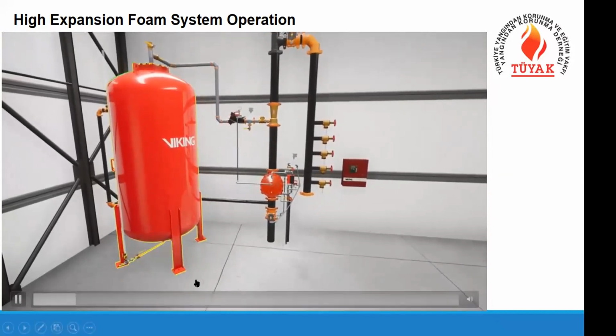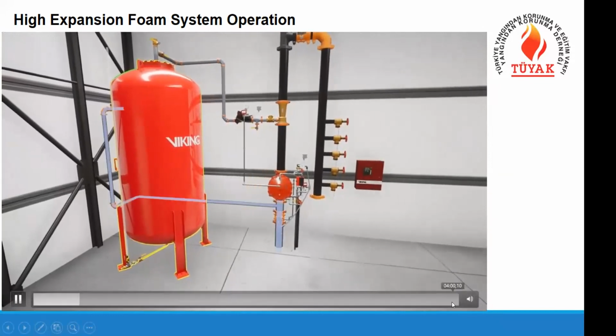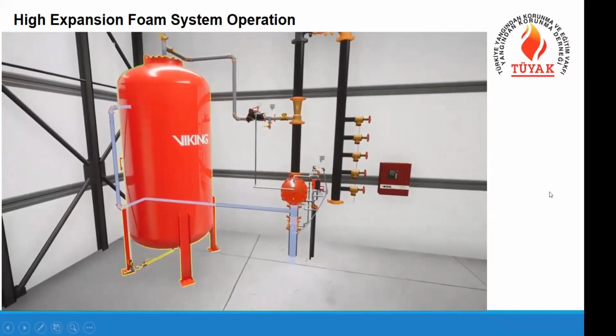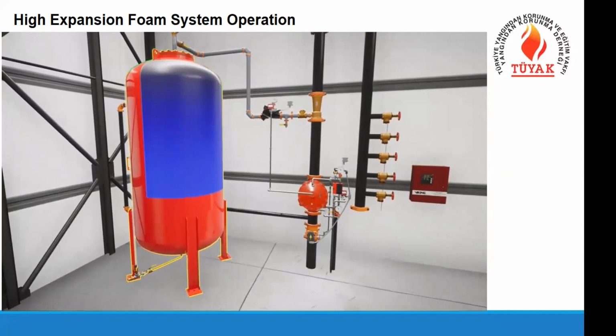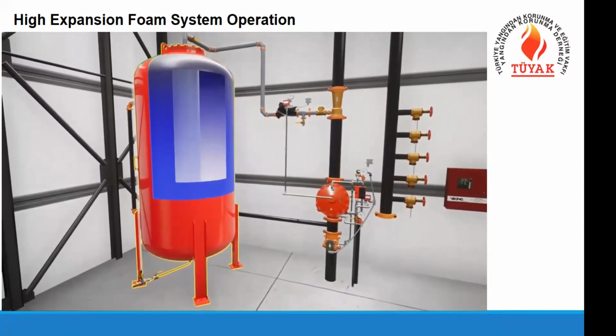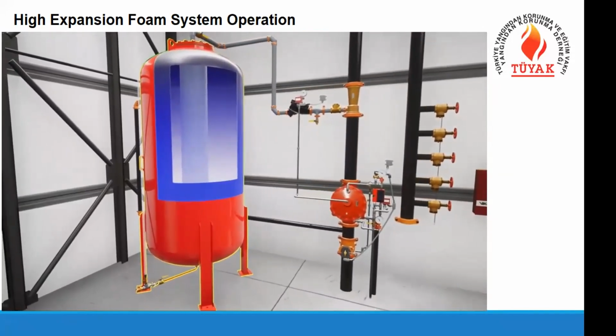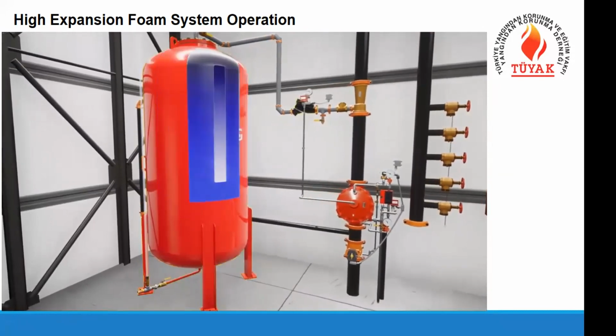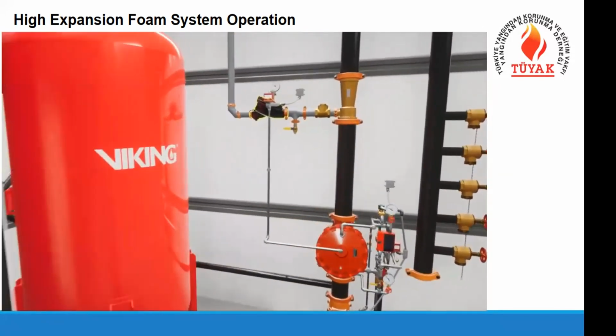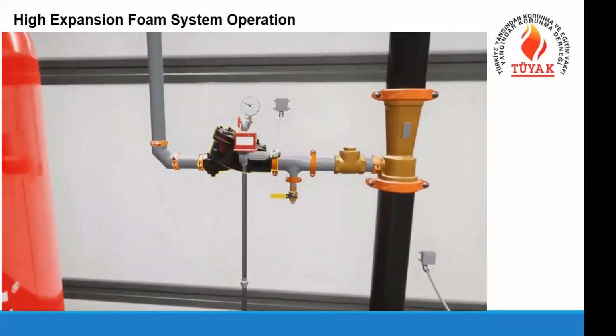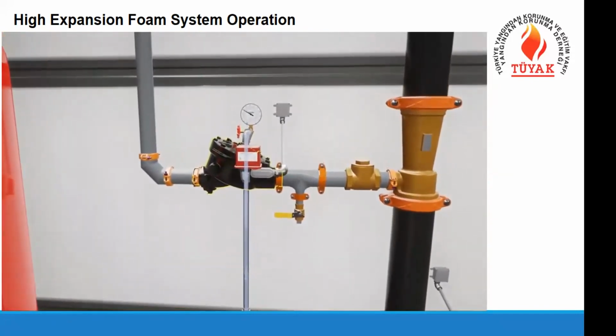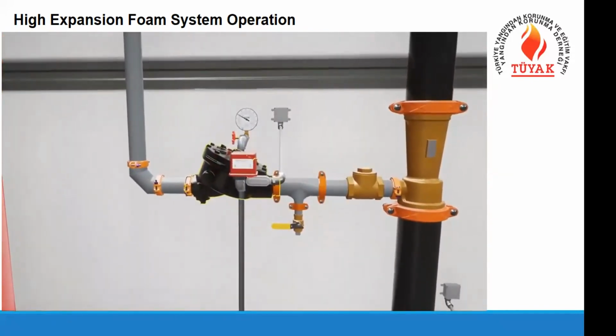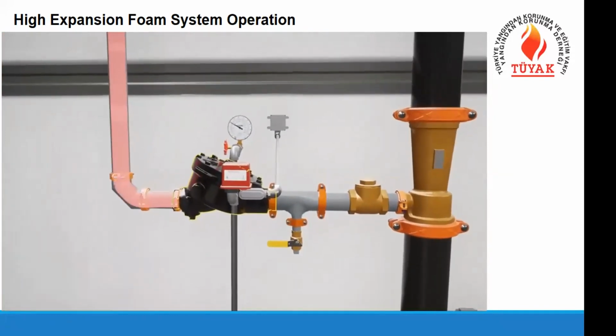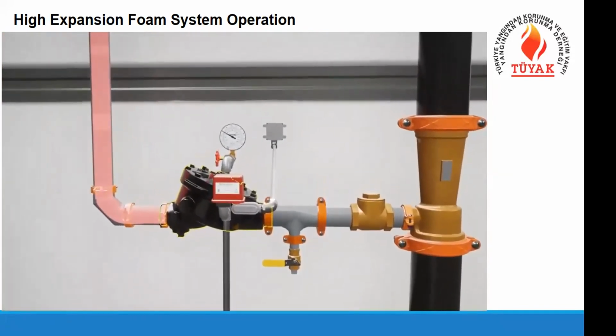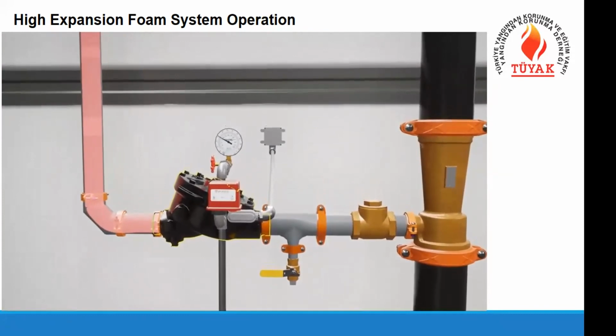A bladder tank is a device that is continually pressurized by the main water supply. The water sits between the steel shell and the rubber bladder. The bladder is filled with a foam concentrate. The bladder tank concentrate piping leads to the concentrate control valve that is held closed by priming water. The concentrate control valve is holding back the foam concentrate supply until the system is activated.